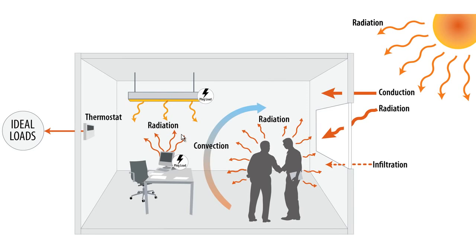In a more complex example, instead of our building being a single zone, we have a number of zones next to each other. On this side, where we have conduction from outside, this would be an outside boundary condition. If we had another zone above us, that would be something called a surface boundary condition, where you have another zone acting upon it, and EnergyPlus will calculate the heat transfer between those zones just as it does outside.